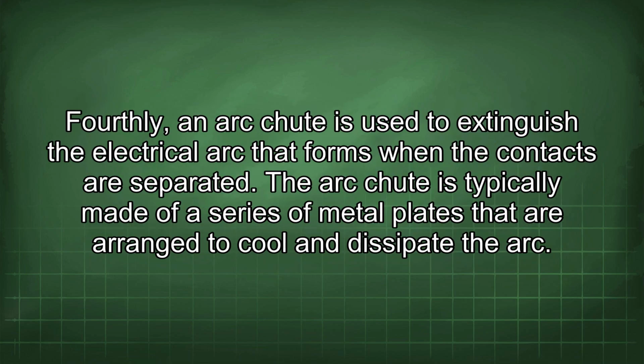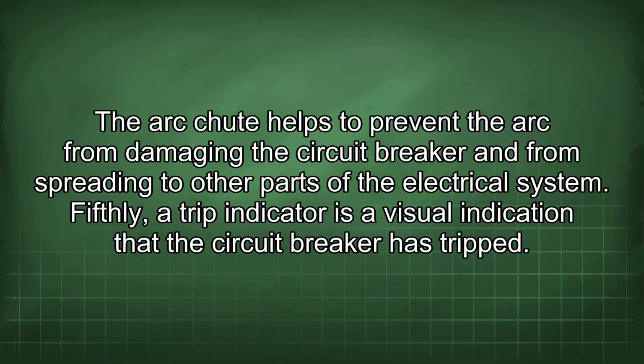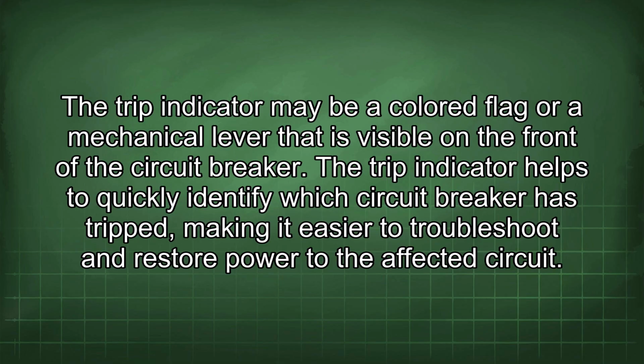Fourthly, an arc chute is used to extinguish the electrical arc that forms when the contacts are separated. The arc chute is typically made of a series of metal plates that are arranged to cool and dissipate the arc. The arc chute helps to prevent the arc from damaging the circuit breaker and from spreading to other parts of the electrical system. Fifthly, a trip indicator is a visual indication that the circuit breaker has tripped. The trip indicator may be a colored flag or a mechanical lever that is visible on the front of the circuit breaker. The trip indicator helps to quickly identify which circuit breaker has tripped, making it easier to troubleshoot and restore power to the affected circuit.